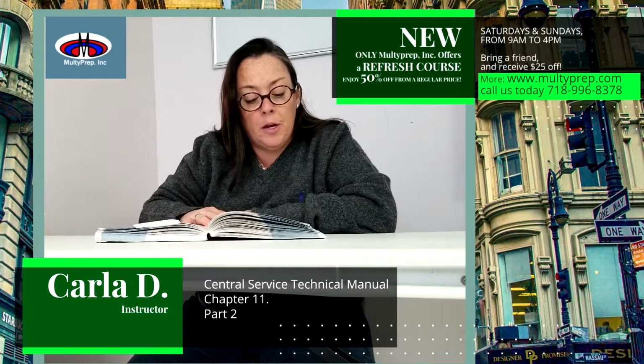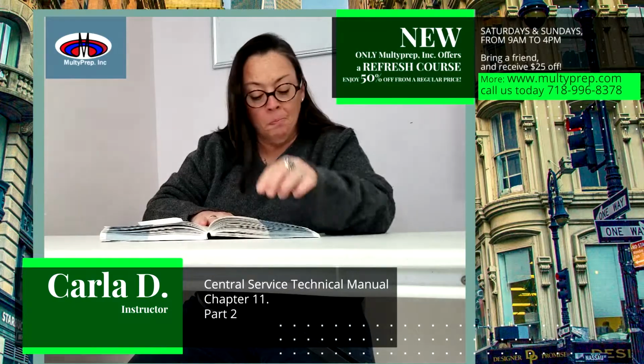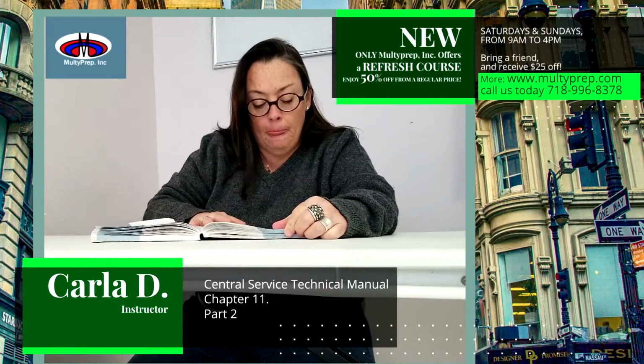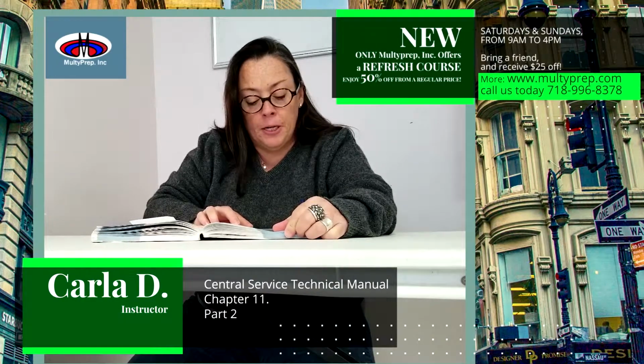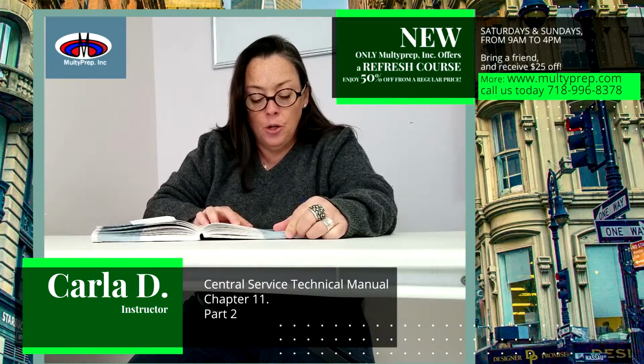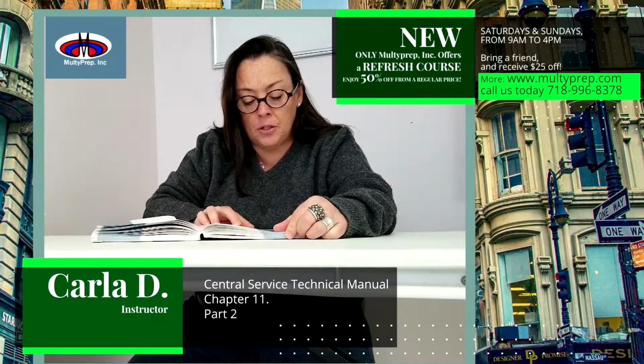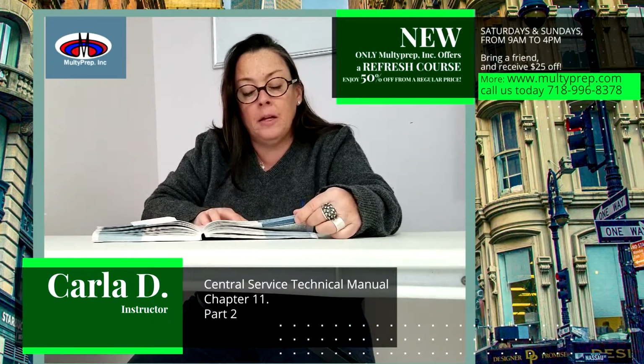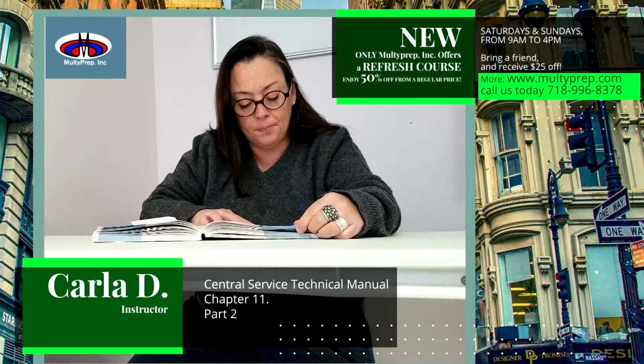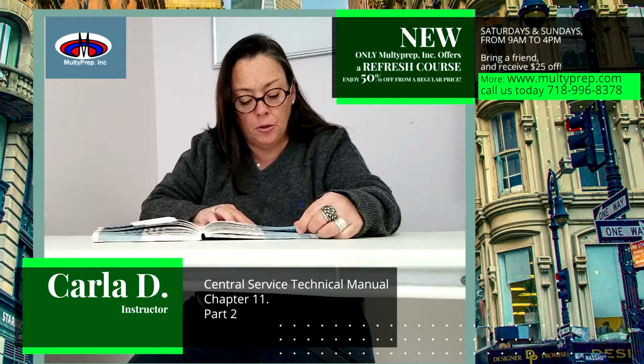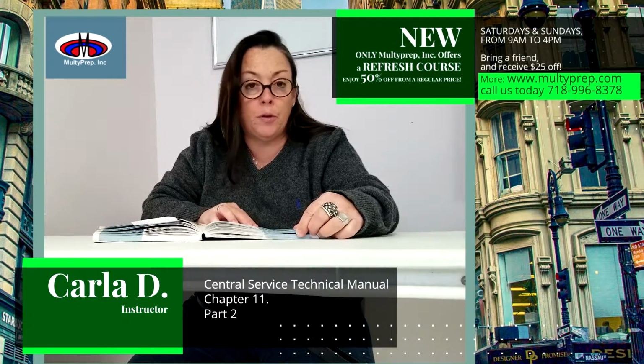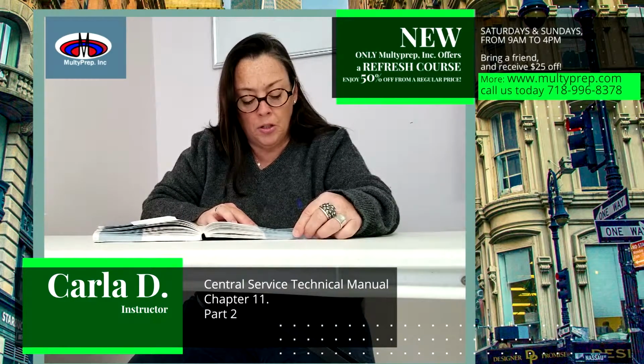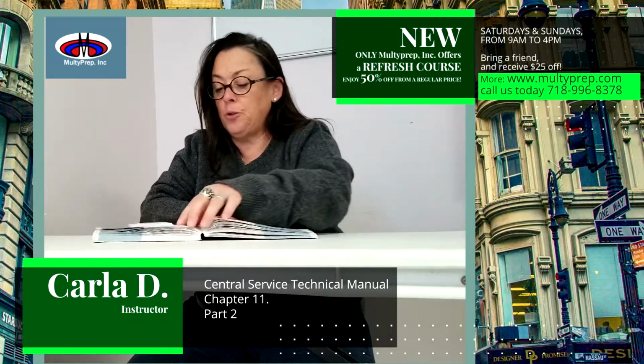I'm going to read you how to create a decontamination battery. Locate a dead, unrepairable battery for each style of powered surgical instrument. Use instrument marking tape to mark a red X on the battery packs and keep these batteries in the decontamination area. An example of this is in Figure 11.19. When battery-powered equipment enters the central service decontamination area, select and insert the appropriate battery pack to protect the electrical components from moisture. Note, while this does help prevent moisture from entering the unit, care should still be taken to avoid contact with excess moisture.